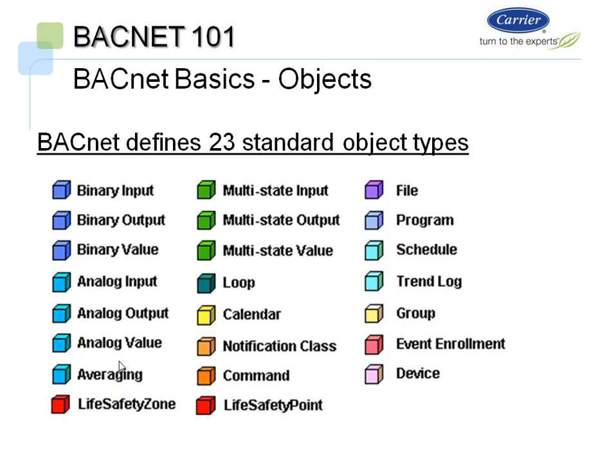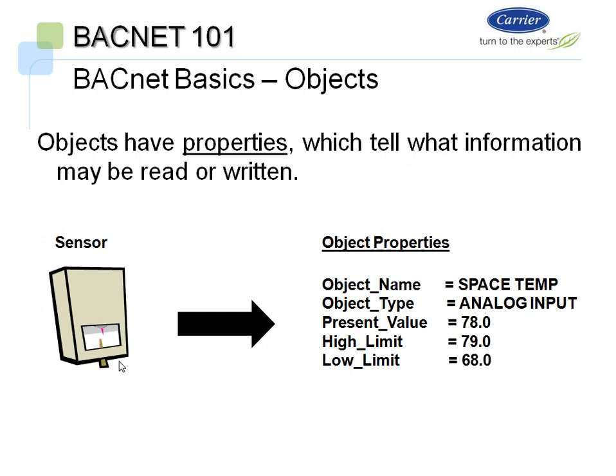I'm going to go one slide quicker here. You can see these are the 23 standard objects that are defined by BACnet. We have binary inputs, outputs, like I mentioned before, calendars, schedules. These are just the standard objects, standard ways to represent data or information on your control system. Going back a slide here, each object has properties associated with it.